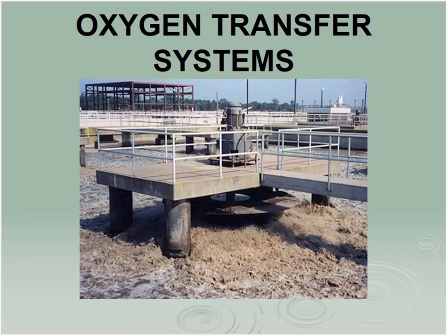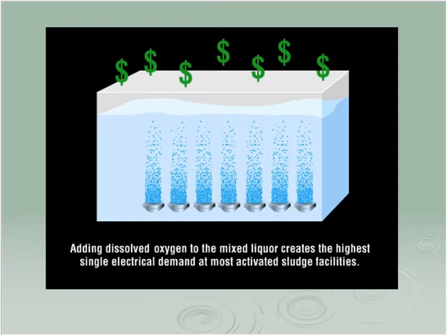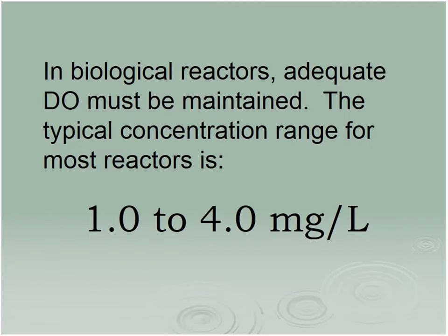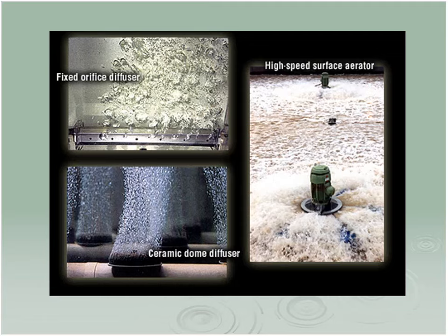It's the big mixmaster thrown into the middle of your tank. This particular part of the process is the most expensive thing that we do. We spend huge amounts of money on electricity to aerate these organisms. Okay, 1 to 4, ideally 2 to 4, and hopefully we've got very good control over that now.